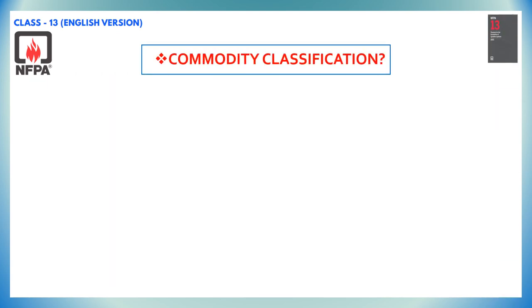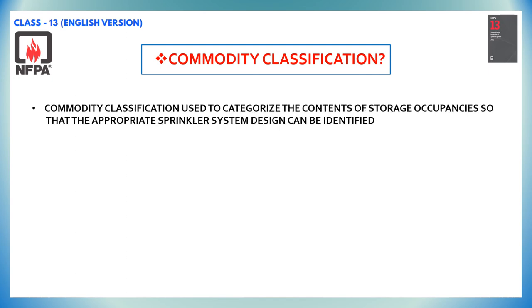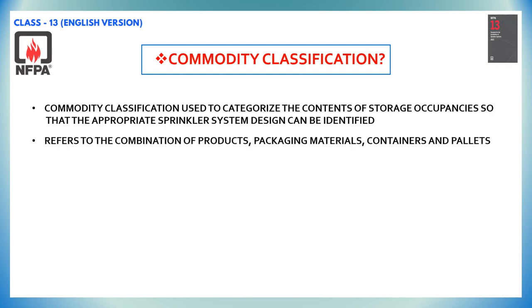Commodity classification is used to categorize the contents of storage occupancies so that the appropriate sprinkler system design can be identified. Commodity classifications are determined by not only the product but also the packaging of that product, the container those packaged products are in, and even the pallet type.